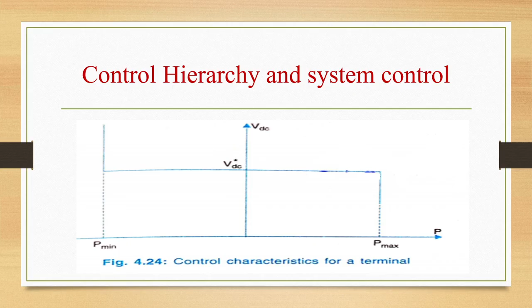Rectifier voltage controller will be given a reference which is equal to VDC at the inverter plus the voltage margin. Operating point is determined by the intersection of the two characteristics as shown in figure A. The inverter determines the power flow as long as it does not exceed the upper limit of the power flow at the rectifier. If the limit on the power flow at the rectifier is exceeded, voltage control will be shifted to the inverter automatically as shown in figure B.